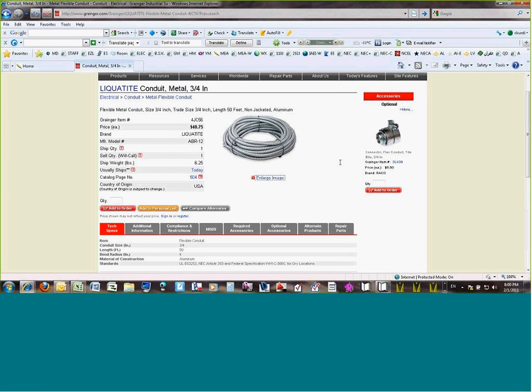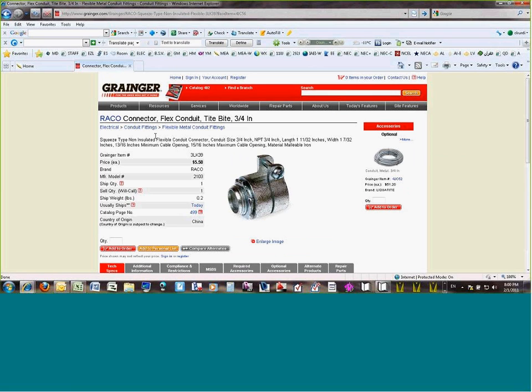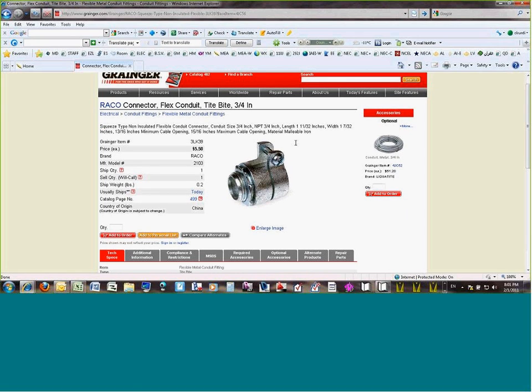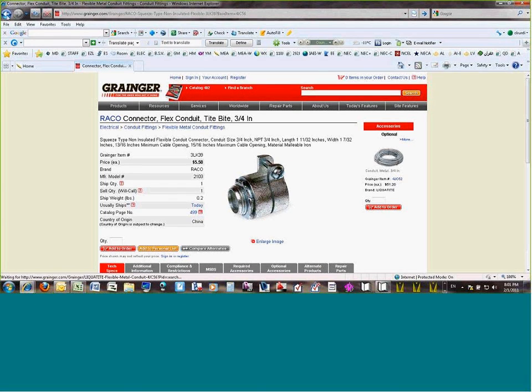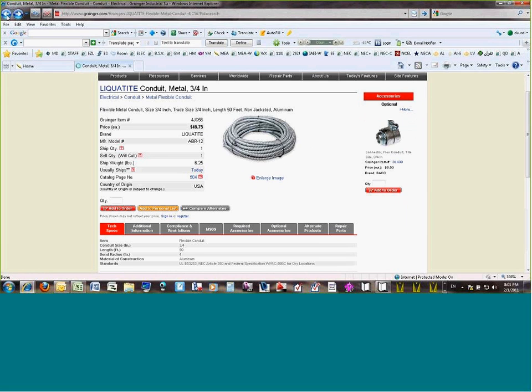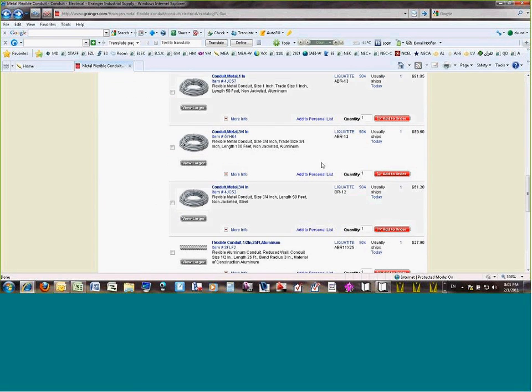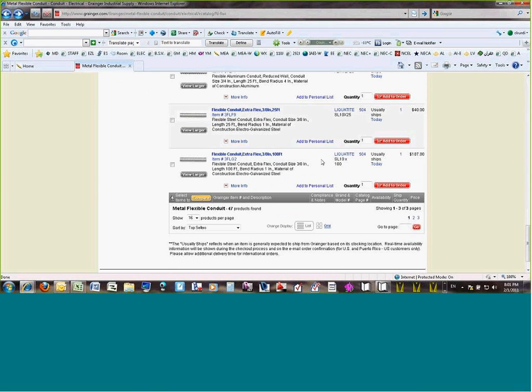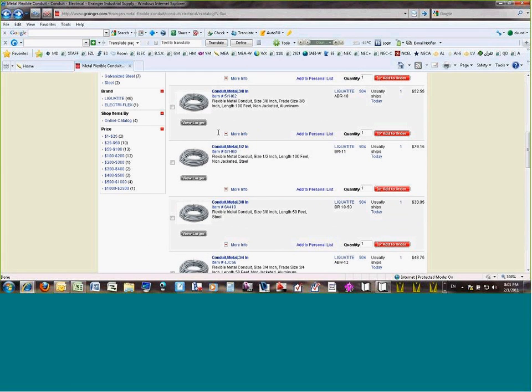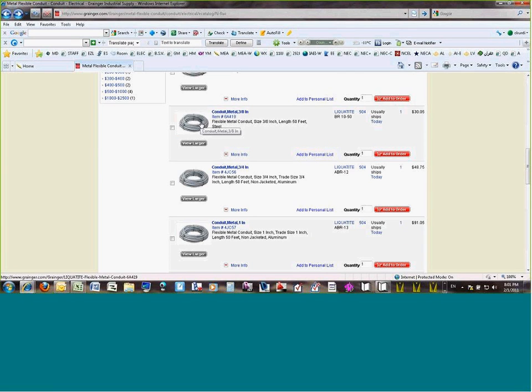So, okay, connectors. If you haven't seen the connector, a lot of us have installed the connectors, guys. It says type non-insulated flexible right here, flexible connector. As you see, you tighten right on it, so you can't use any connector other than a flex connector with a flex equivalent. So that's what we see here. A few things about the flex that I thought we could go over. So that's my flex. I'm going to do steel again.